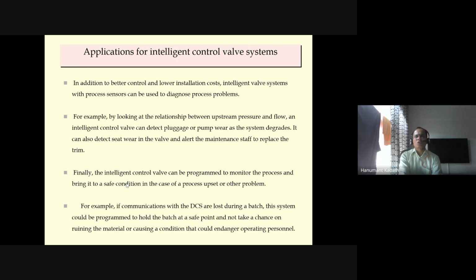In addition to better control and lower installation cost, the intelligent valve system with the process sensors can be used to diagnose process problems, because it has the sensors, temperature, pressures. Through that you can diagnose the process variability. For example, by looking at the relationship between the upstream pressure and flow, an intelligent control valve can detect a pluggage or pump wear as the system degrades. It can also detect seat wear in the valve and alert maintenance staff to replace the trim. So you can plan the maintenance, knowing the valve is degrading based on upstream and downstream performance and flow rate.